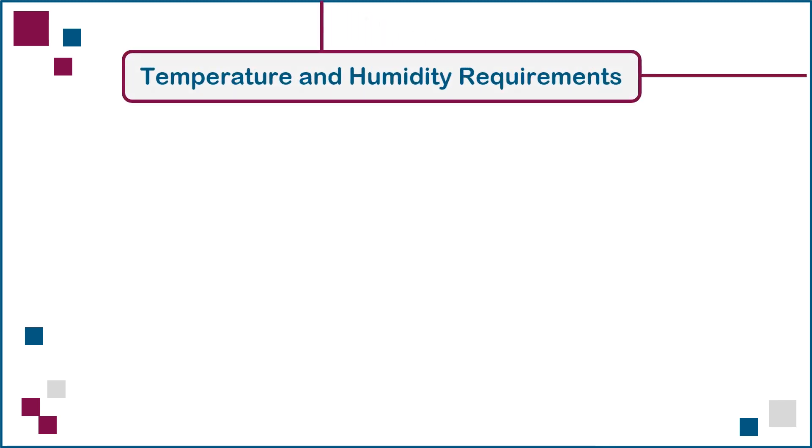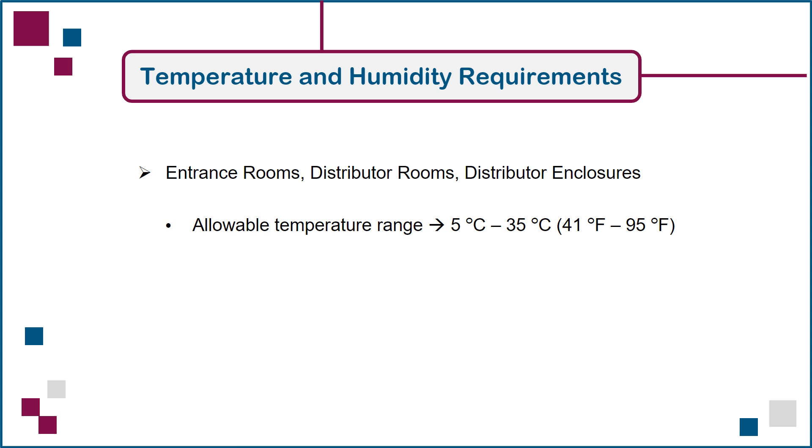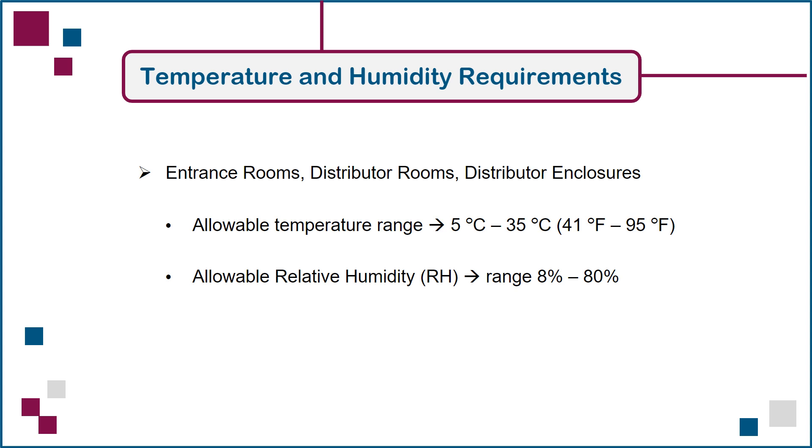We'll finish off this lecture with a look at temperature and humidity requirements for telecommunications spaces designed to contain powered network devices. The allowable temperature within spaces such as entrance rooms, distributor rooms, and distributor enclosures should be no less than 5 degrees Celsius and no greater than 35 degrees Celsius at all times, preferably with low variation over time. Similarly, the relative humidity in these spaces can range from 8 to 80%. Note that these values can accommodate most network equipment, but there are always exceptions which may require tighter ranges or limits in specific spaces.